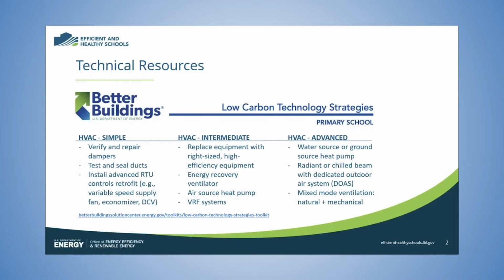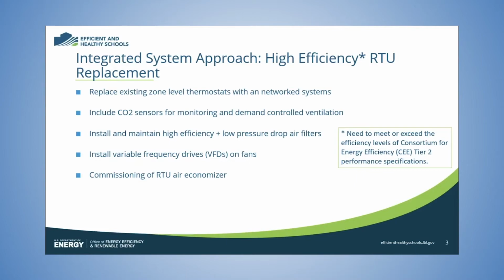If you are retrofitting or replacing your system, we're really encouraging schools to use the integrated system approach. So first, start with high efficiency equipment. Be really explicit in your performance specification on what efficiency standards you want to hit, and then layer on top measures that can get you further. For example, you will want to replace your existing thermostat with a networked system, and better if you can include your CO2 monitoring, and better if you can do those filter rack designs that Sonia was showing you, so you can achieve high efficiency, low pressure drop air filtration.